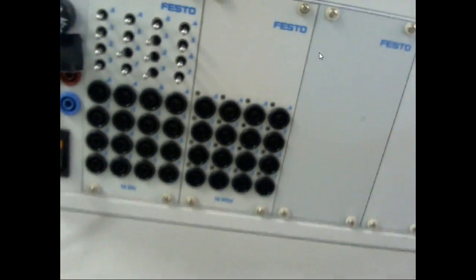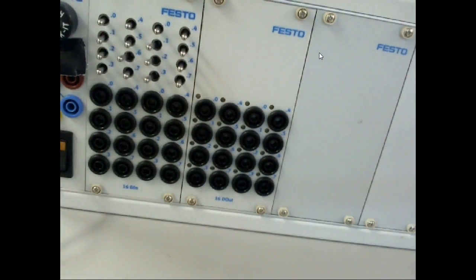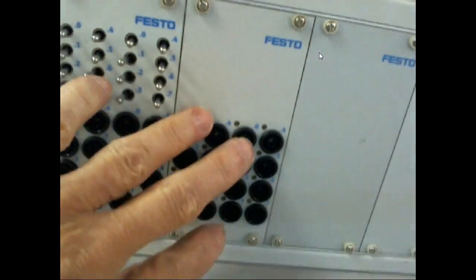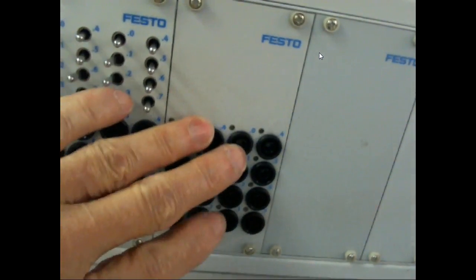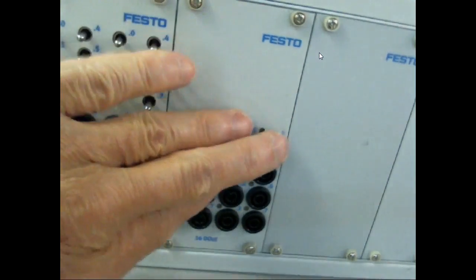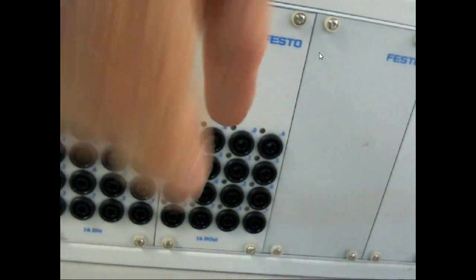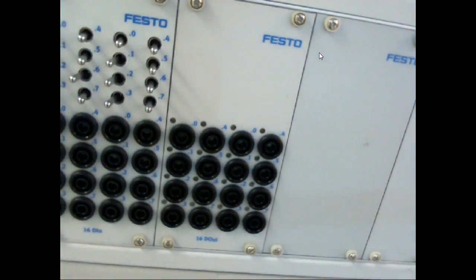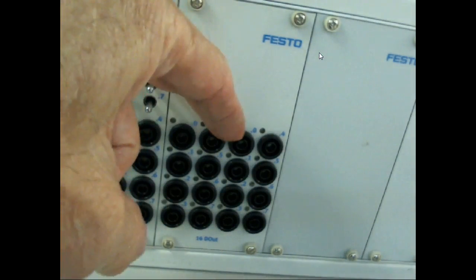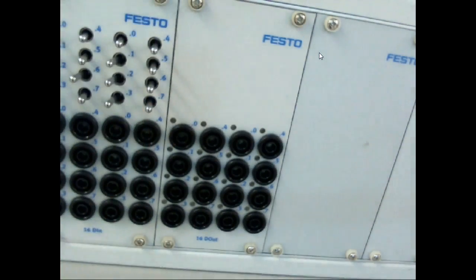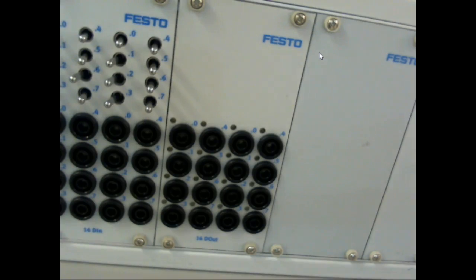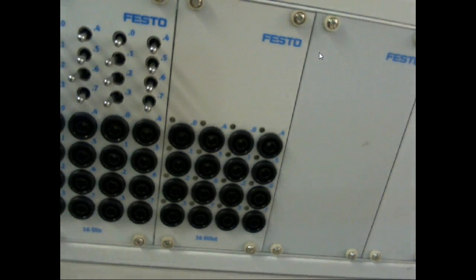Okay? Now, why do we do that? Well, all these switches are sourcing switches. So if my switches are sourcing, then by George, I better set up my PLC input to be what? Sinking. And all these output ports right here, I'm sorry, these are sourcing. So sinking inputs, and these are sourcing outputs. That makes sense? Or did I tie that up?